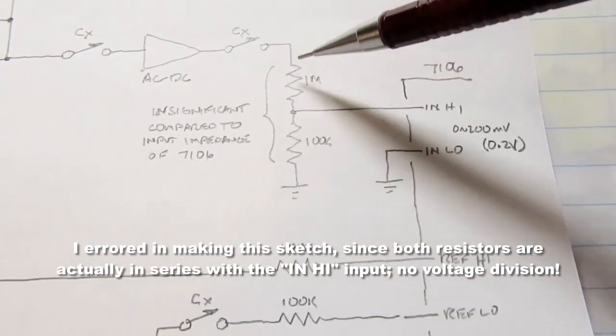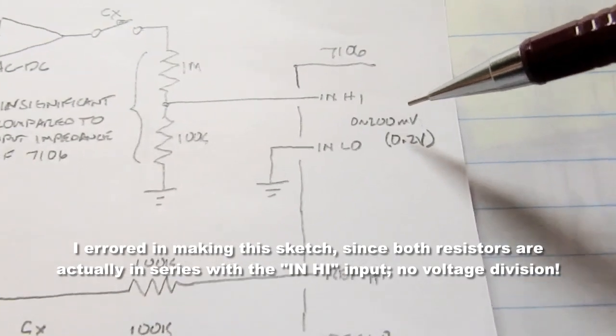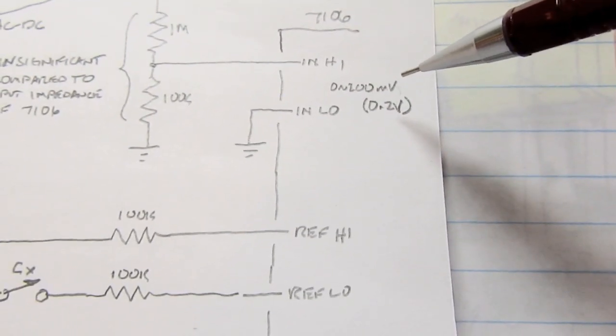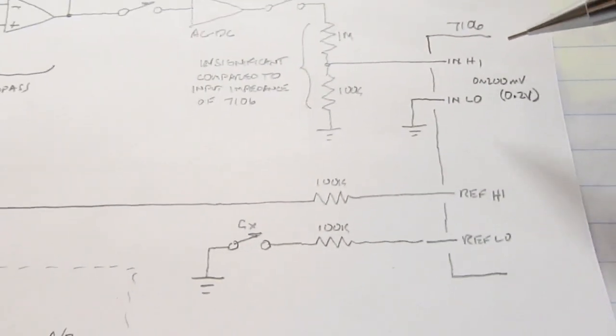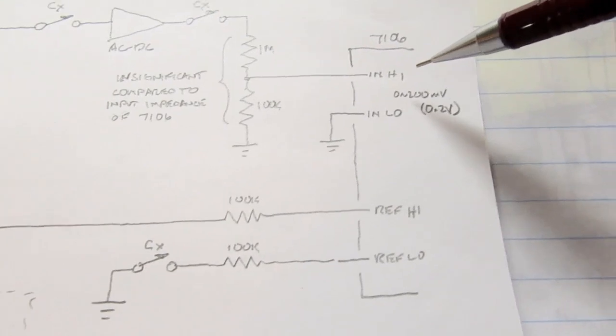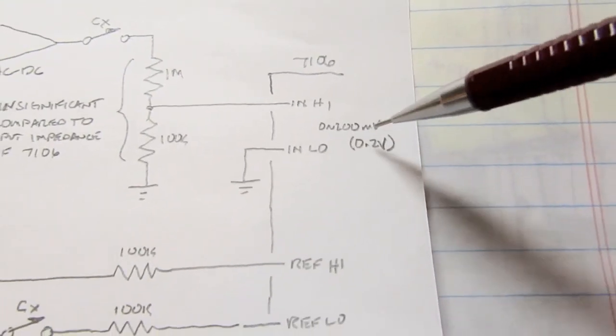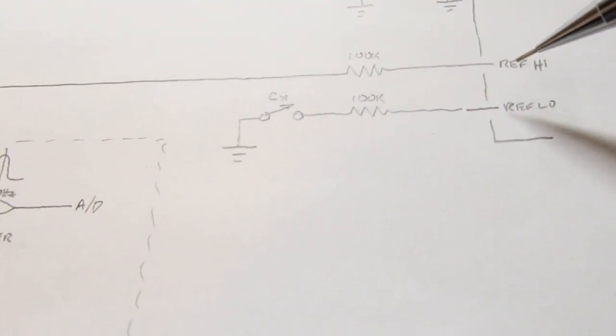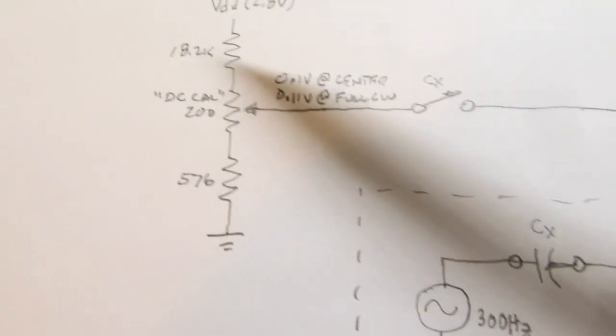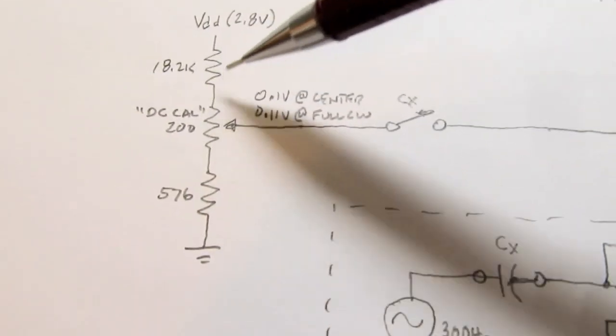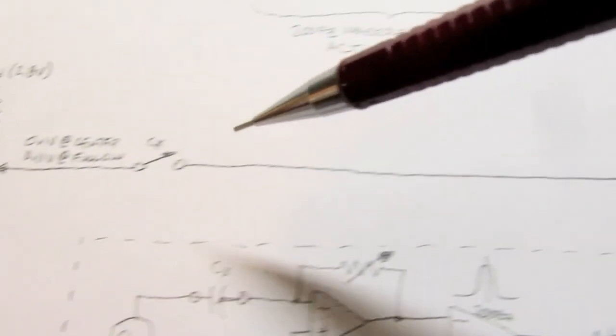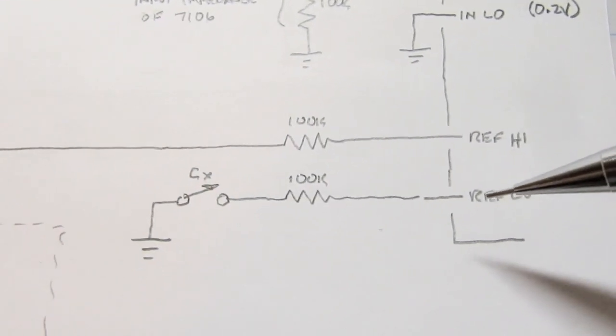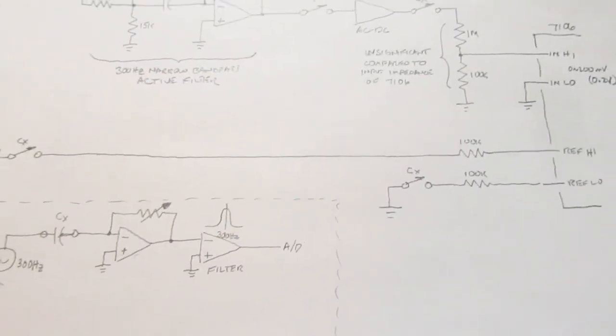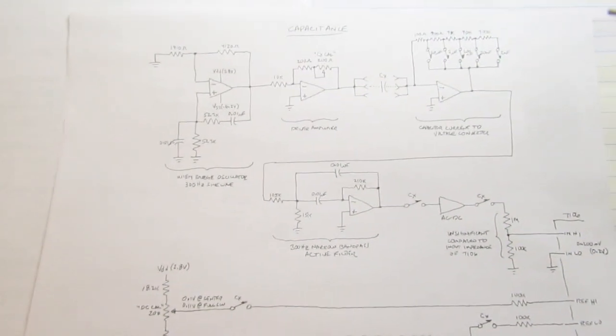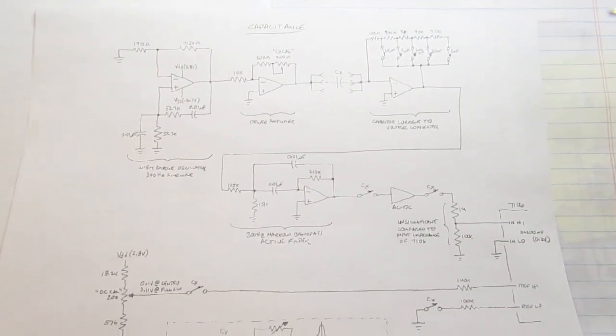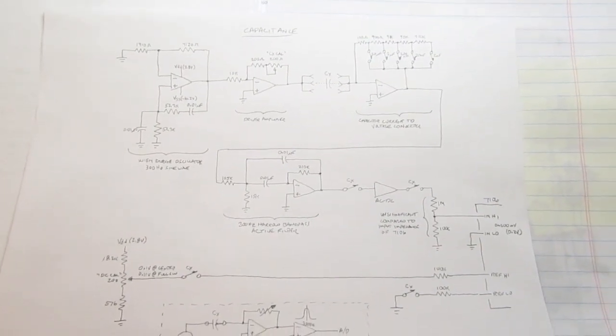We once again have that insignificant pair of resistors, and it comes in here and it's treated as a 0 to 200 millivolt signal. It is DC, and it's got to be in that range. Now the reference voltage here, again, it's done just like it is on the other simpler modes. You've got the DC cal voltage tapped off of the VDD and applied to the reference high, and the reference low is just connected to circuit common. So that's all there is there. Converting capacitive reactance to voltage and then measuring that voltage, and thereby knowing the capacitance.